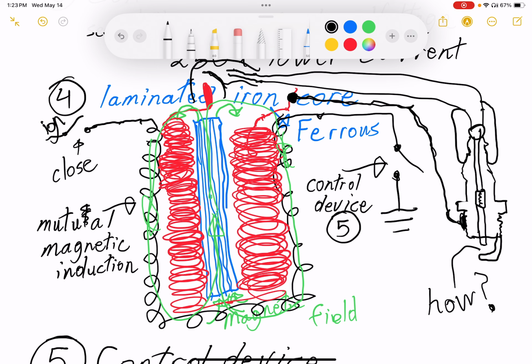So when you get that proper magnetic field and it becomes a saturated magnetic field, we'll talk about that more in a bit, you end up with around 250 times more volts in the secondary than you have in the primary. Now, the primary is going to run at around that 10 volts, or at a lower voltage than operating voltage, so that it can control the magnetic field.